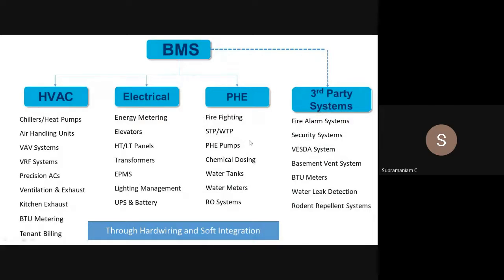So if we see in the background, BMS, going deeper into it, it will have this kind of structure. One is the HVAC vertical, another is electrical, another is PHE plumbing, another is third-party systems. Now under HVAC we have chillers, air handling units, VAVs, VRF, precision ACs, ventilation. And under electrical, you have all this energy metering, elevator, whatever goes into the building. In simple terms, whatever MEP equipment, mechanical, electrical, plumbing, that we have, it can be brought to BMS by either field controllers or factory controllers. Like PHE, you take STP, chemical dosing, all those kinds of things, and third-party systems.